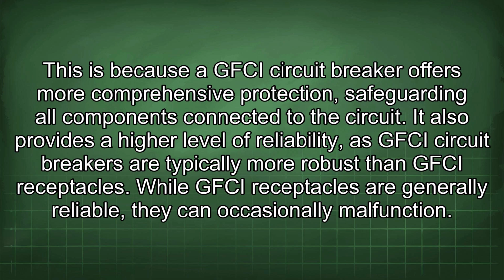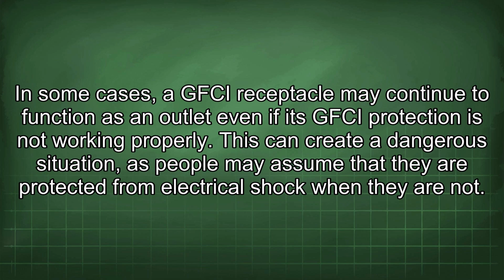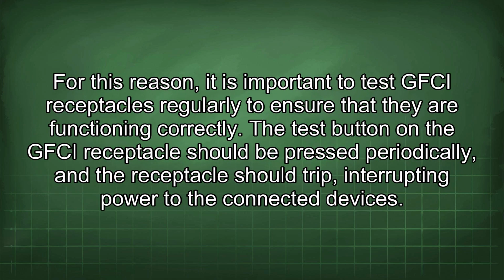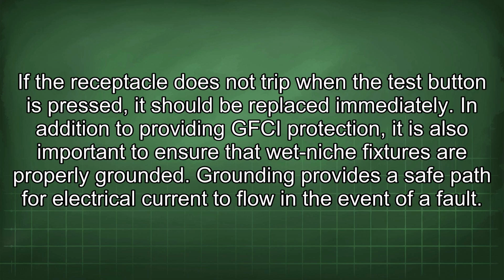While GFCI receptacles are generally reliable, they can occasionally malfunction. In some cases, a GFCI receptacle may continue to function as an outlet even if its GFCI protection is not working properly. This can create a dangerous situation, as people may assume that they are protected from electrical shock when they are not. For this reason, it is important to test GFCI receptacles regularly to ensure that they are functioning correctly. The test button on the GFCI receptacle should be pressed periodically, and the receptacle should trip, interrupting power to the connected devices. If the receptacle does not trip when the test button is pressed, it should be replaced immediately.